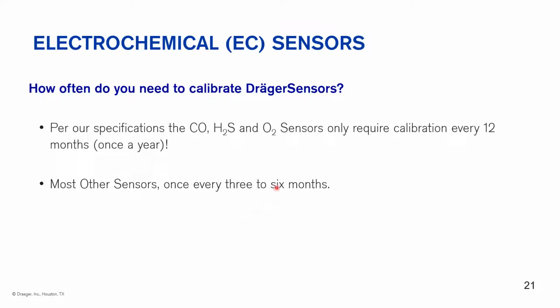So calibrations, per our specs, the big three, CO, H2S and O2, only require calibration every 12 months. Other sensors will vary from 3 to 6 months. This is dependent on the units and the sensors being function tested or bump tested as they should be, basically daily prior to use.